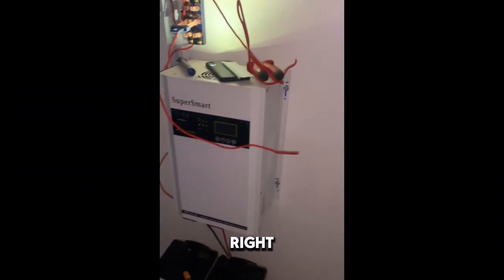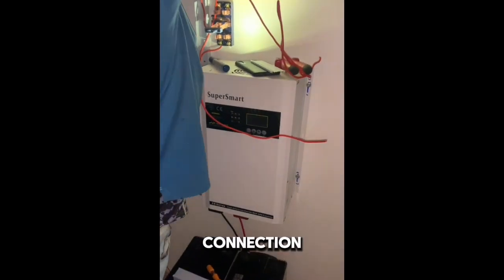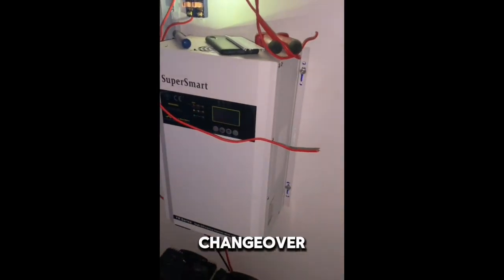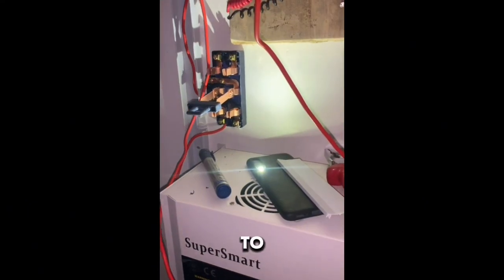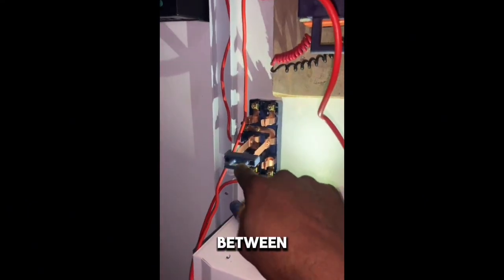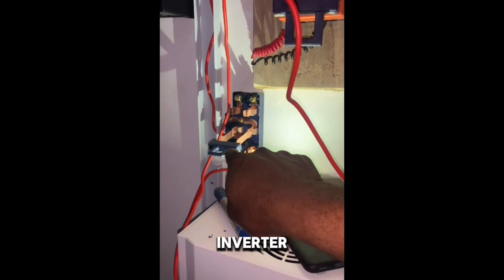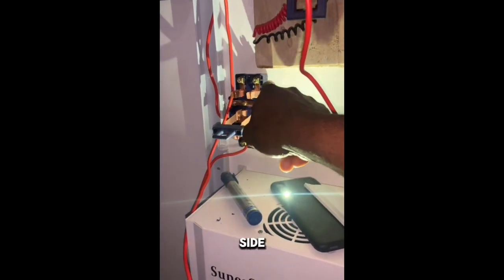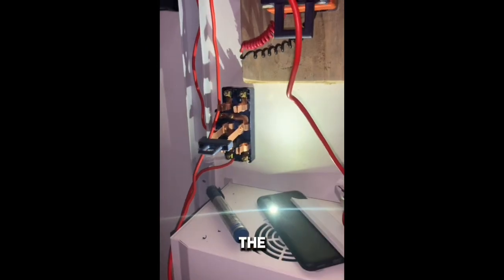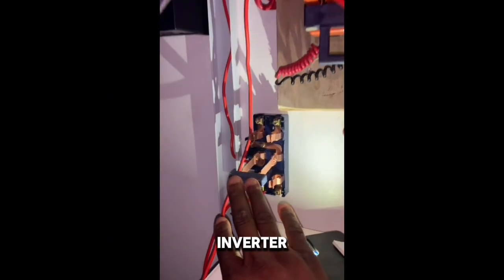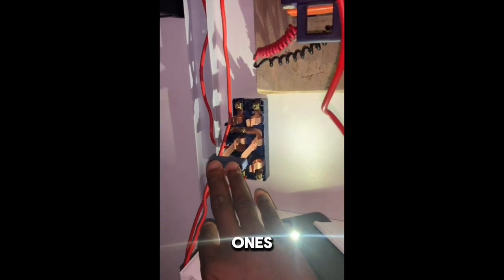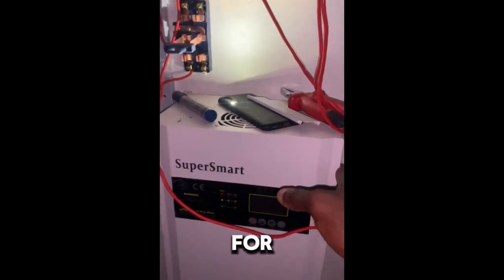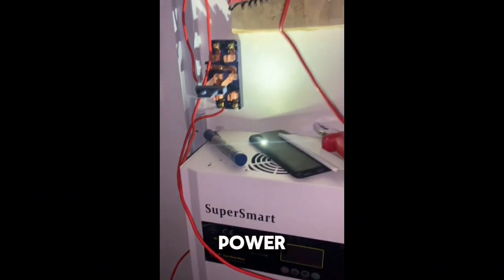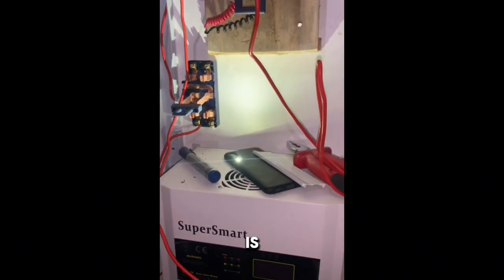All right. Here I'll be explaining the connection for what you use your changeover for. The changeover you'll have here, this very one, is only to switch between a bypass and the inverter. The top side is going to be for the bypass, the bottom is going to be for the inverter. Not like the regular ones most installers do. They say the top side is for the grid, that's when there's power, when power is restored, while the bottom is for the inverter.